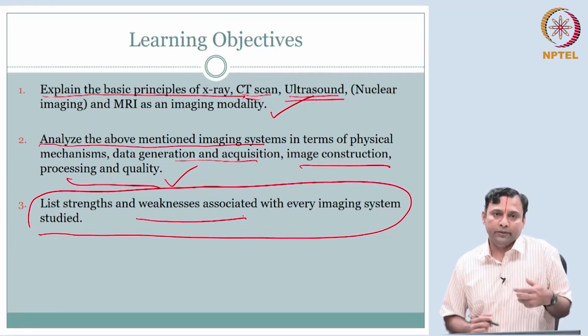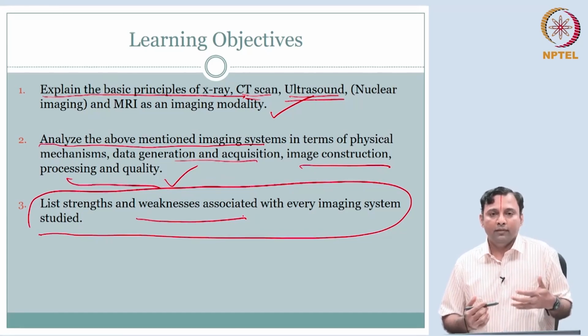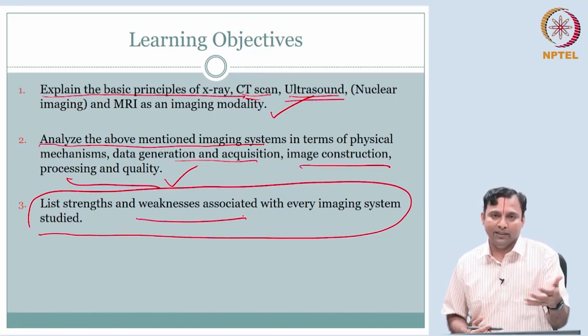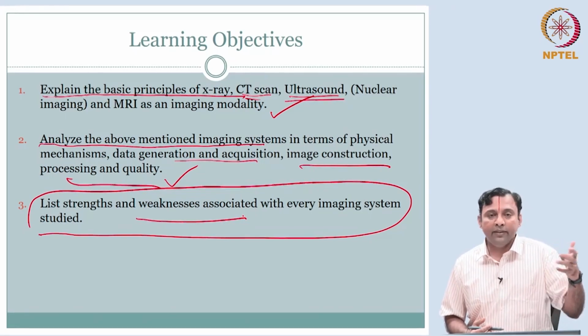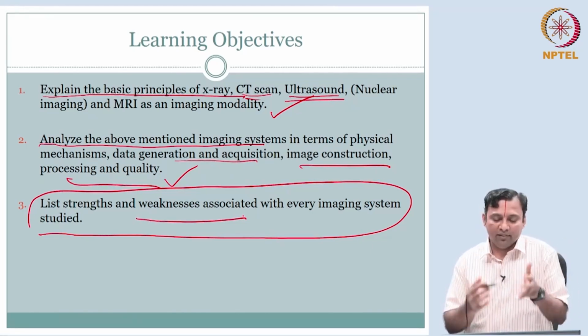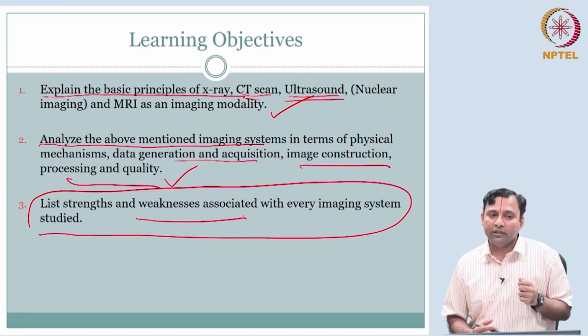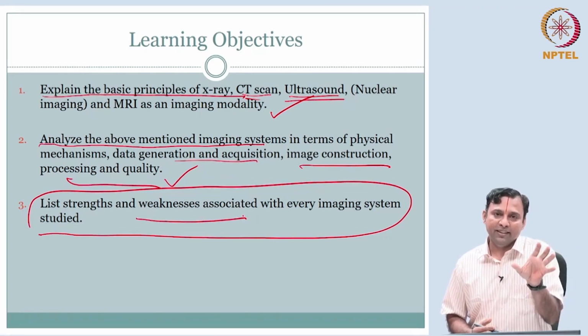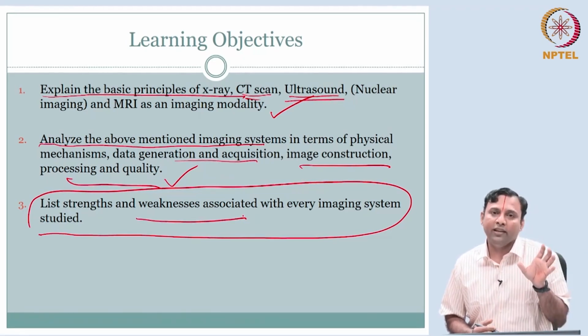So you should be able to clearly articulate and understand that, so that it is not only good for you, because you will become comfortable in making your choice, but also for the person whom you are advising. A doctor could say, they released the latest scanner last month, and they are saying this gives superb image quality. As an engineer on board, you should be able to say, these are the specifications, these are probably cosmetic, it's just marketing language, there is no fundamental change in quality.